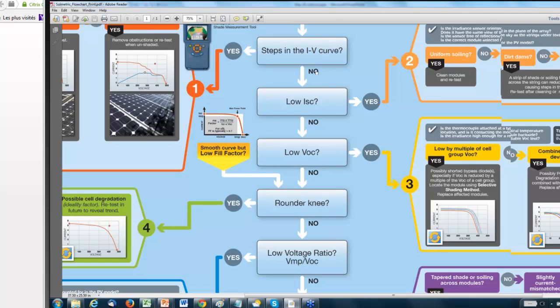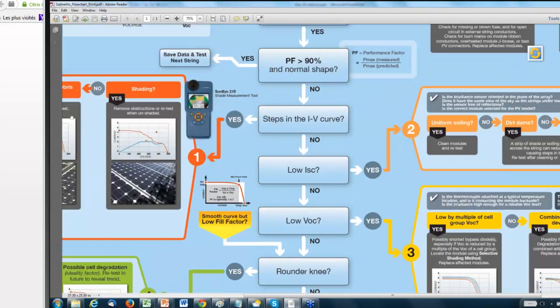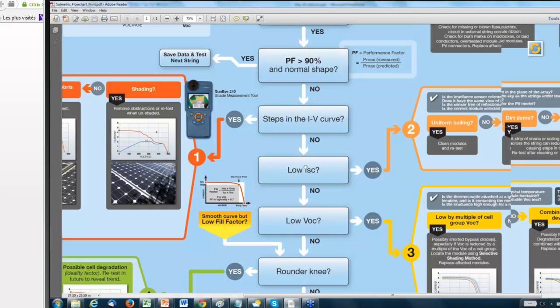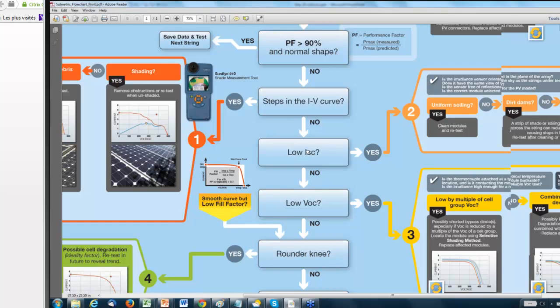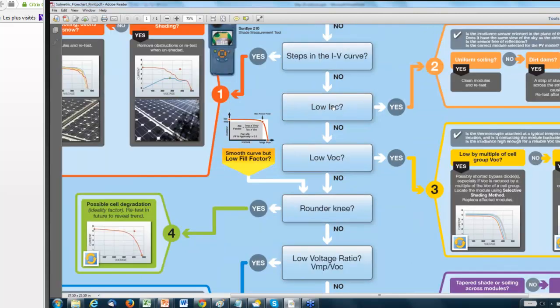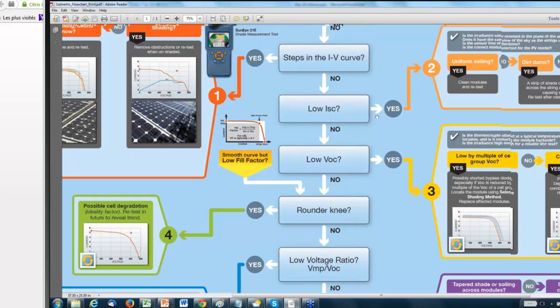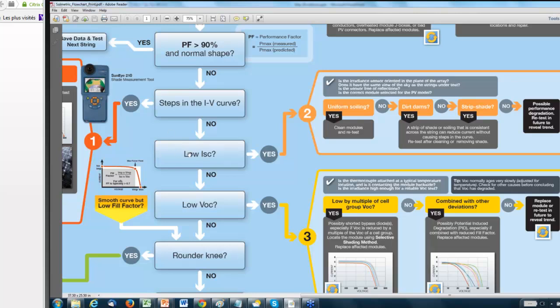So suppose we did not see any steps in the IV curve. Then, of course, we would not go to the left on orange number 1. We would drop straight down and check to see if it has a low short circuit current. And the reason I put this next is because a lot of times people will use their irradiance sensors improperly. They won't be facing in the plane of the array. They'll be pointing straight at the sun, or they'll be pointing straight up, lying on the ground or on the roof, and not necessarily in the angle of the array itself. So we'd like to get that problem out of the way early as well.